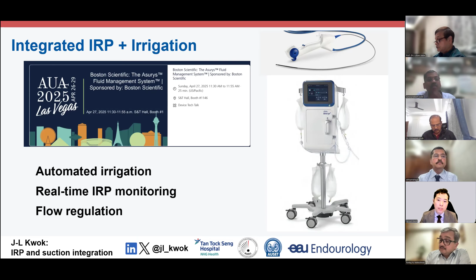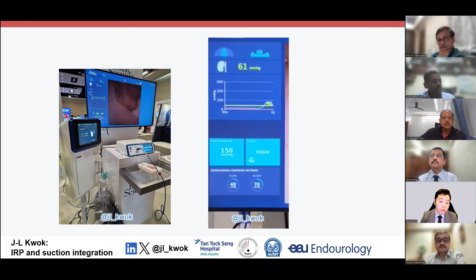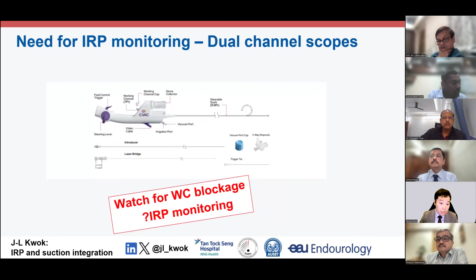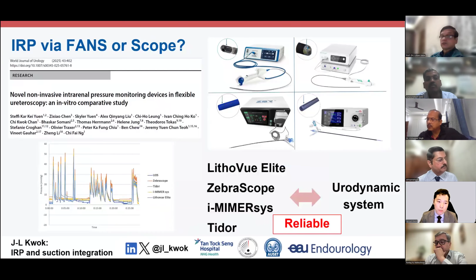So the need for IRP monitoring, particularly in dual channel scopes, may be important. If you have a dual channel scope with one way in and another way out, if your outflow is actually blocked and you don't know about it, your continuous inflow may cause very high intrarenal pressures. And if you don't measure that, it may not be very good for the patient. So IRP via FANS or scope, this is a paper by Dr. Yuen, essentially LithoVue Elite, ZebraScope, the i-MIMERsys system, the Tidor system and urodynamic system, and all seem to have been reliable and quite congruent. So we are quite good in terms of correlation between different machines as well as different ways to measure IRP.